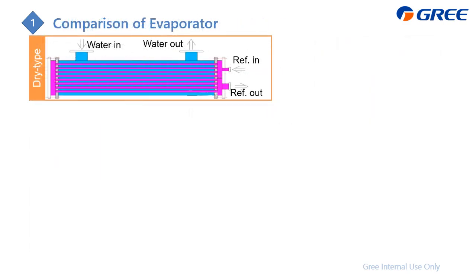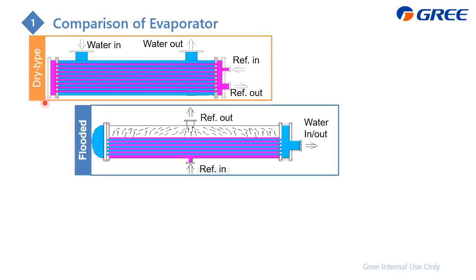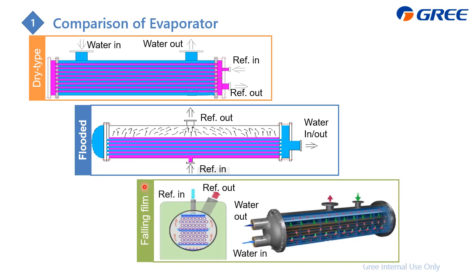And here I compare three types of evaporator, which are the dry type, flooded type, and falling film type. For these three, you can find that the refrigerant and the water, whether in the tube or inside the shell, are different. So for the first, the dry type, the water is in the shell, the refrigerant inside the tube, right? And for the flooded type, the water is in the tube, the refrigerant in the shell. And the same, the falling film is the same as the flooded type. The water in the tube, the refrigerant in the shell.